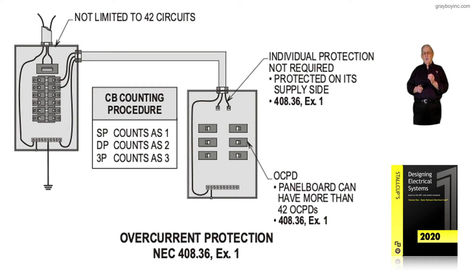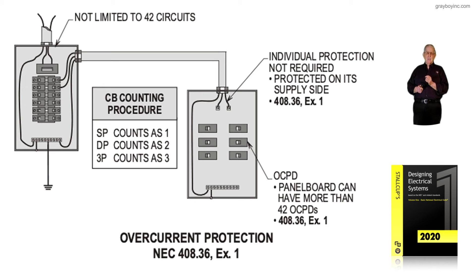But if that panel board was located outside the building — maybe in another building — and that was a feeder routed over to that building, then we would need a disconnect or a main in that panel board in accordance with 225.33 if you're having just a main installed.